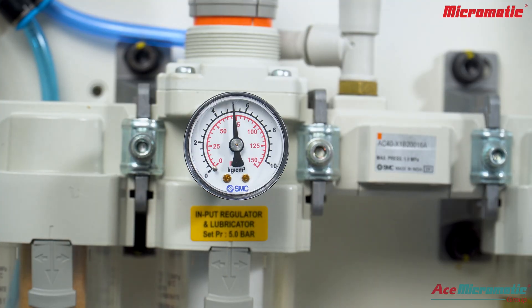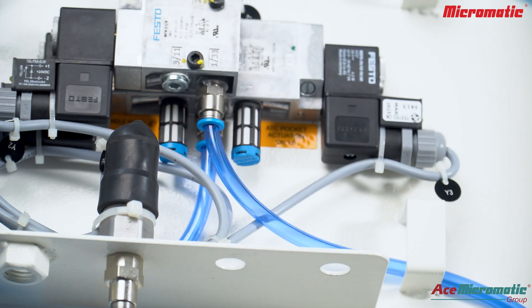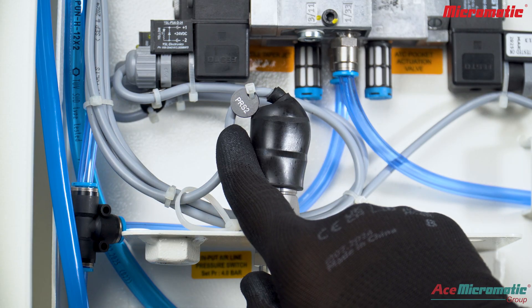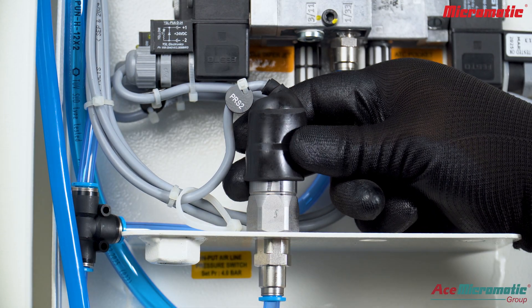In case the pressure is sufficient, inspect the pressure switch, its connections, and the wiring all the way to the electrical panel. Check the wiring of pressure switches and loose connections in the leads.